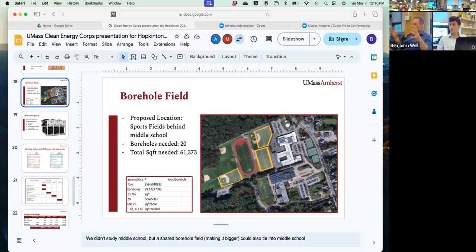So one of the things that could happen is that if you got an ambient loop, right? This is the loop of water that's roughly 50 degrees because it's just exchanging with the ground. Let's say it was a cold day. Let's say the temperature from the ground you're unable to get above, say, 40 degrees because you're sending water back so cold, there's so much demand. And it was just an extreme condition.